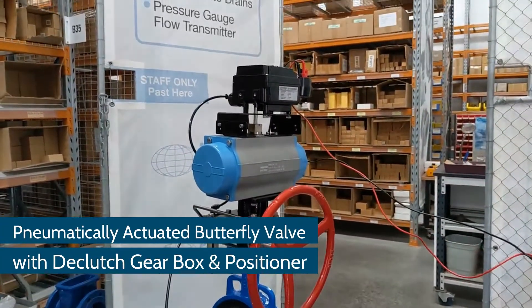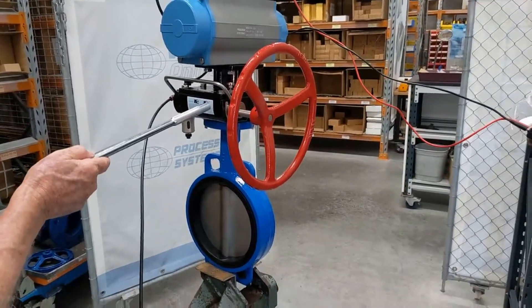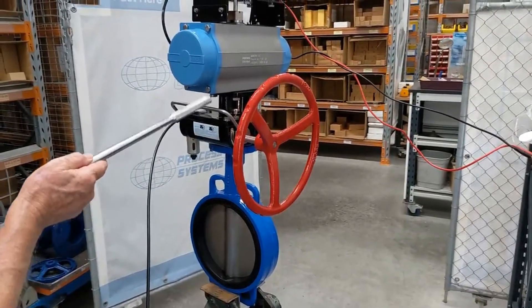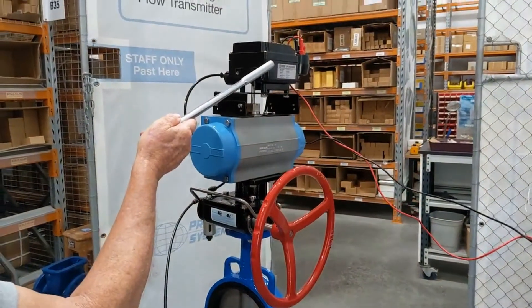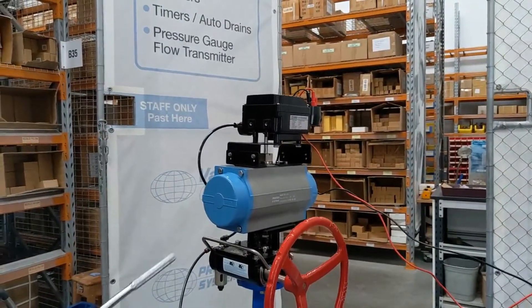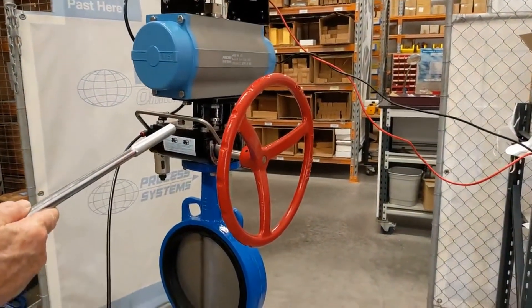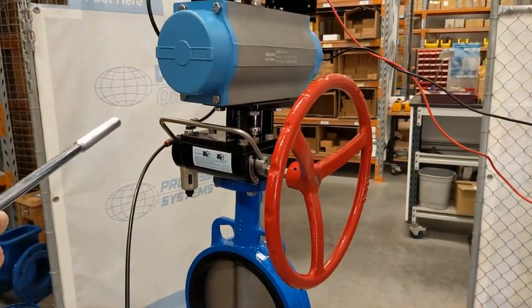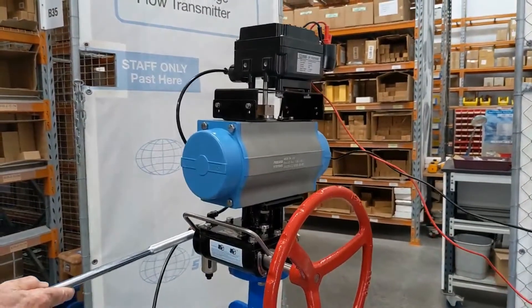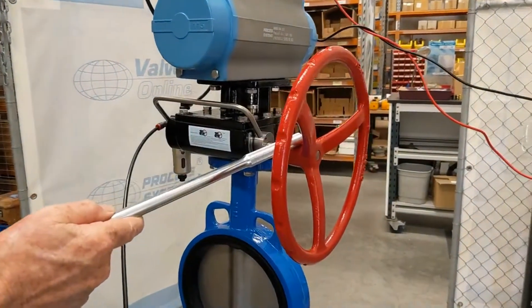This is a BFD butterfly valve with a declutching device, a double-acting actuator, and a 4 to 20 milliamp electric-to-air positioner on top. The advantage of this unit is that we can disengage the pneumatic actuator by exhausting the top unit via a three-way valve at the end of this device, then engage the manual override.